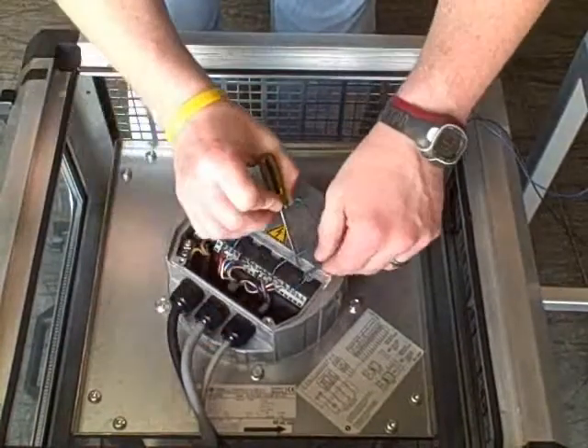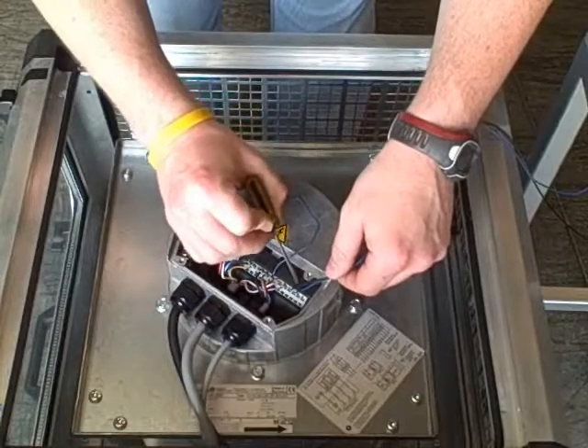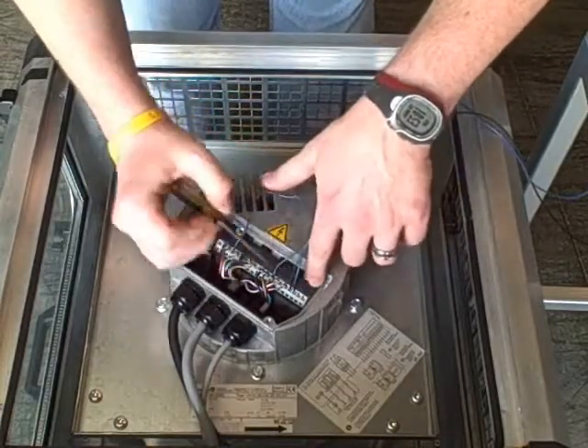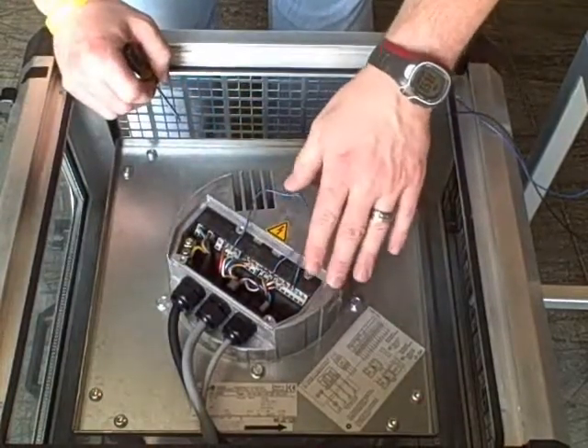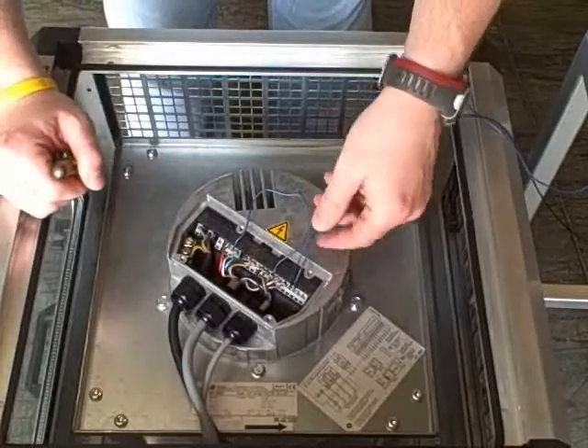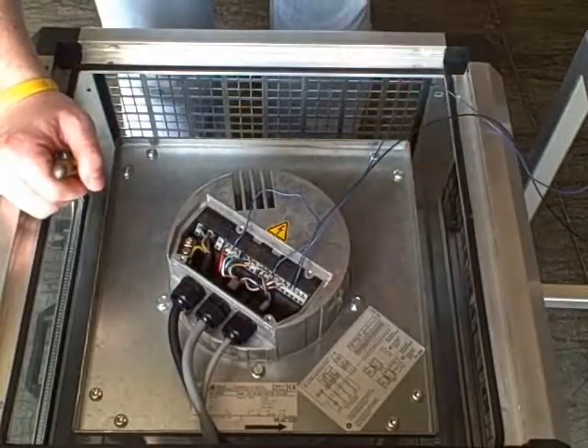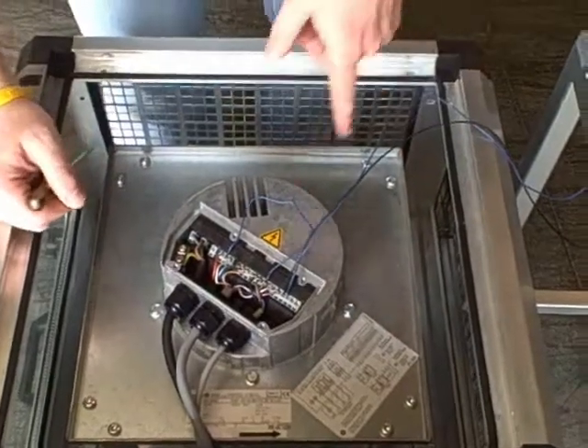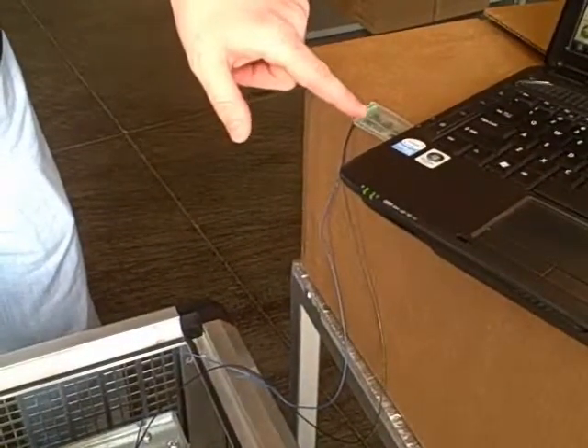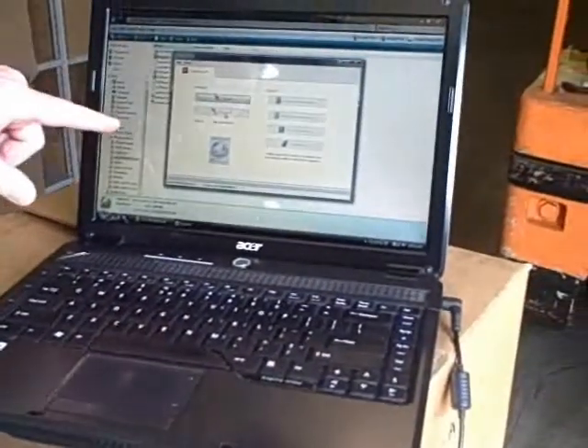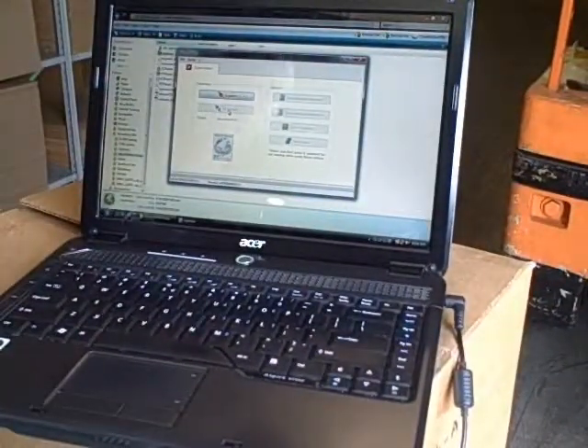What we've done is we've gone ahead and connected it. You've got two sets of contacts like we talked about earlier. You've got an RSA and an RS-B, and then you've got another set of RSA and RS-B connectors. It doesn't matter which ones you use. What we've done here is we've gone ahead and plugged this into our laptop. You'll follow these wires up and notice our USB to RS-485 connector already connected and our EC parameter software already connected and open and ready to go.